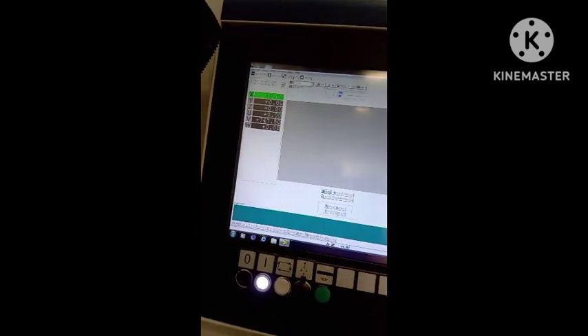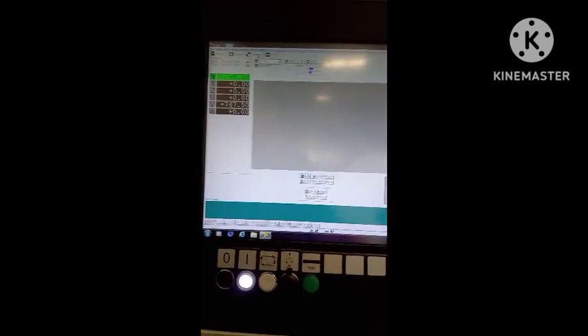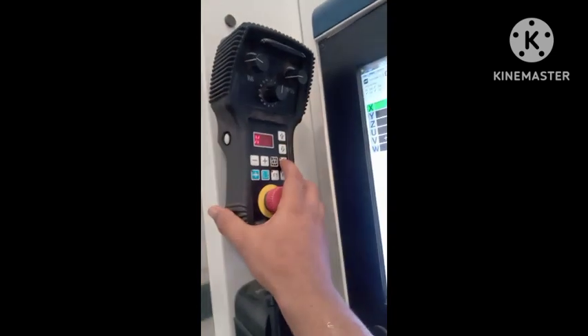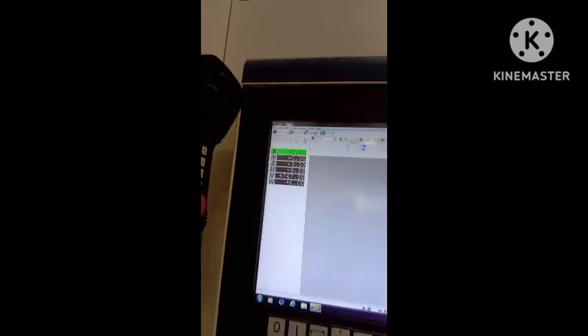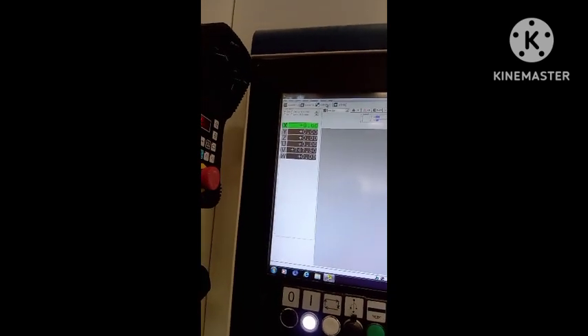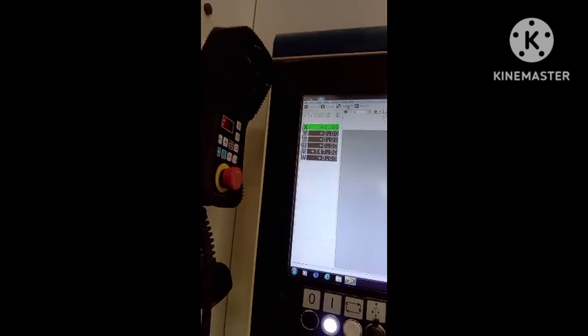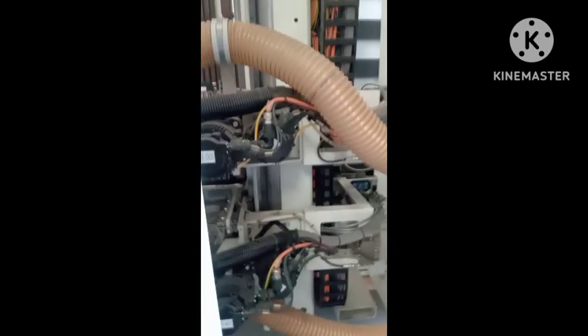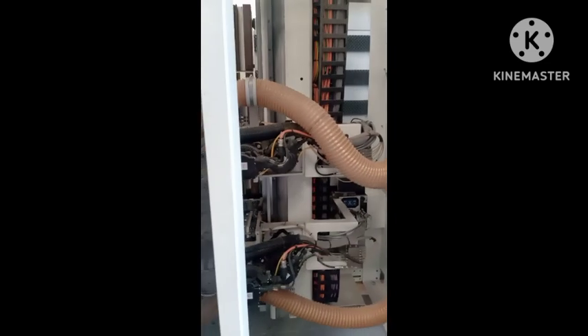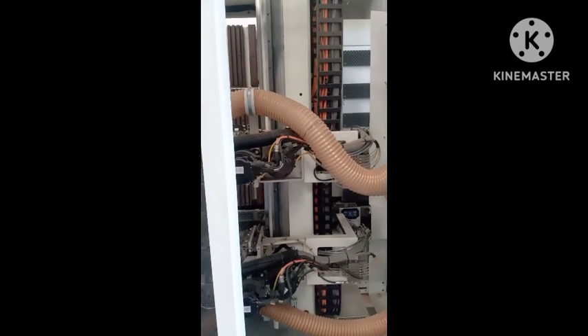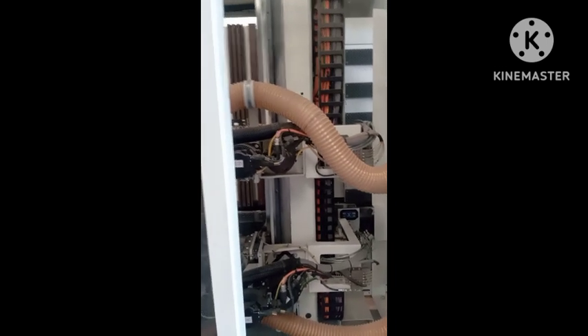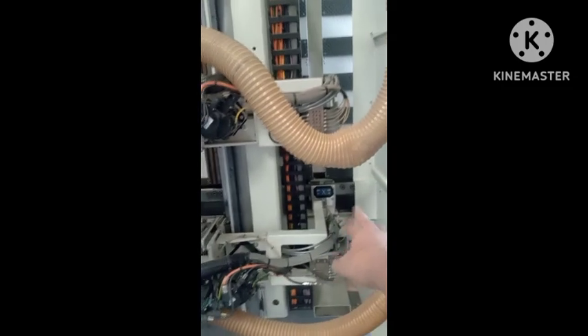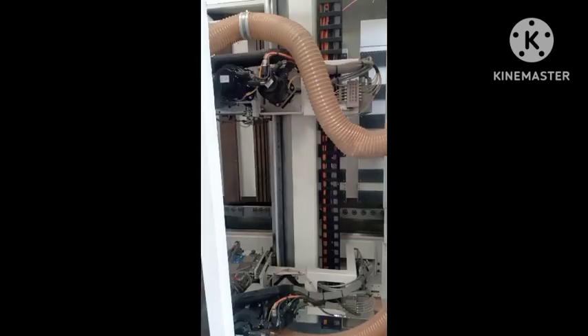Okay, now you can start the calibration, and you will see the motors in moving condition, so you have to press this cycle start button here. Now the machine has started to move. You can see. This X motor will go there, Z down and V up. Let's see the PLC output during this condition.